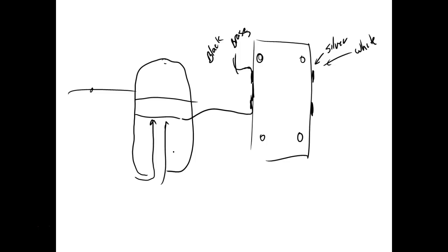So for pneumatics, you have our lockouts for our pneumatic system. You'll hear it when you push it in; it automatically drains the system. But what you need is a pressure gauge out there past your lockout, so you can verify when you lock it out that the pressure gauge is reading 0 psi.